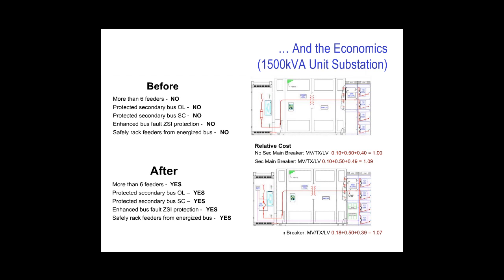And finally, at the very bottom right of this slide, the new approach using a primary vacuum breaker, the medium voltage transformer and low voltage assembly comes out at 1.07. So it's fairly clear that we have almost a push, actually maybe some savings, of the secondary main breaker approach with the fused load break switch primary, as opposed to including a vacuum breaker in the primary used to protect both the primary and the secondary bus. The integrated unit substation, which we spoke of earlier, would also be at about the same price point as the primary vacuum breaker design, but with the advantage being a smaller footprint.